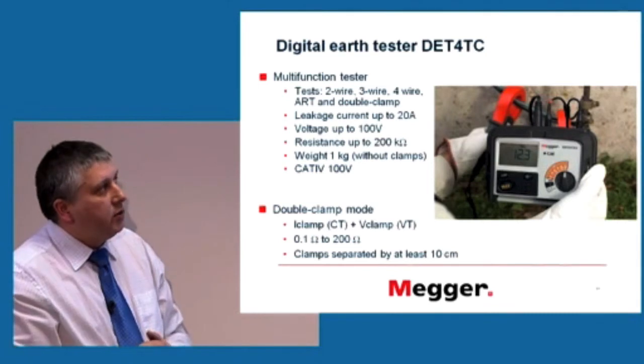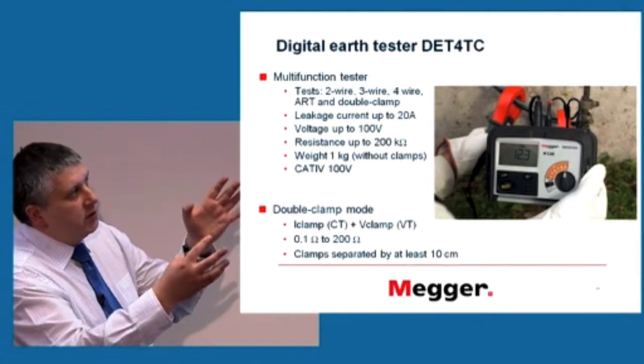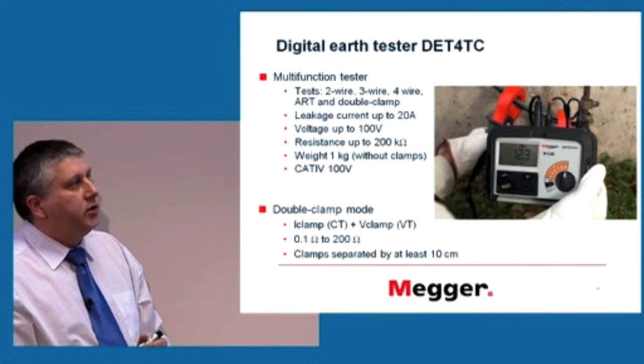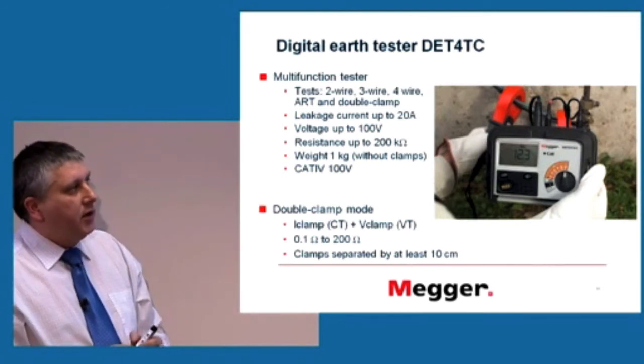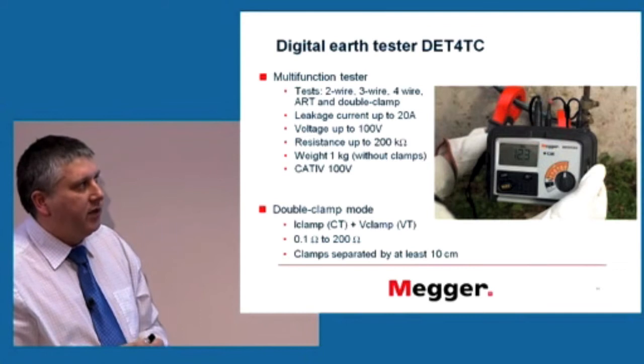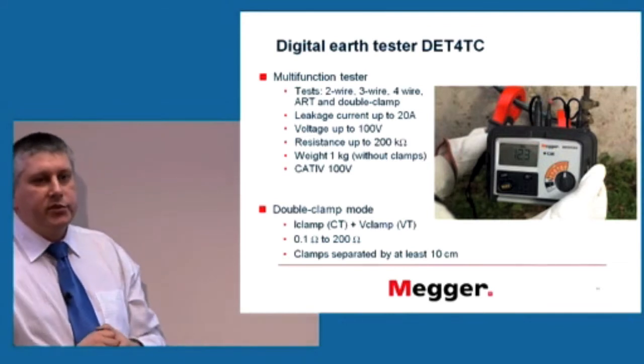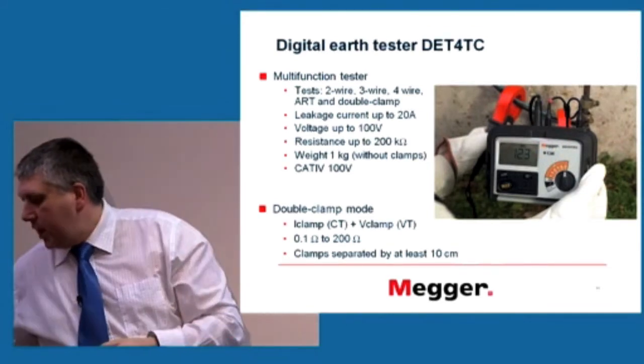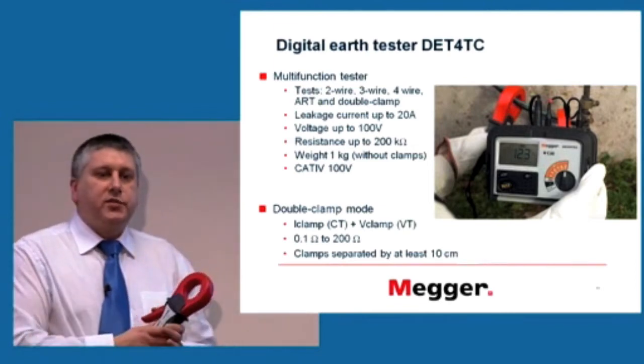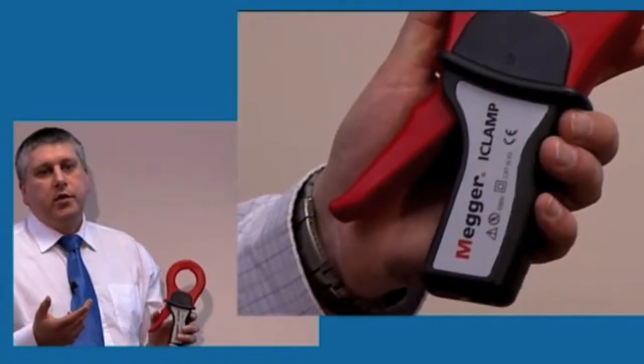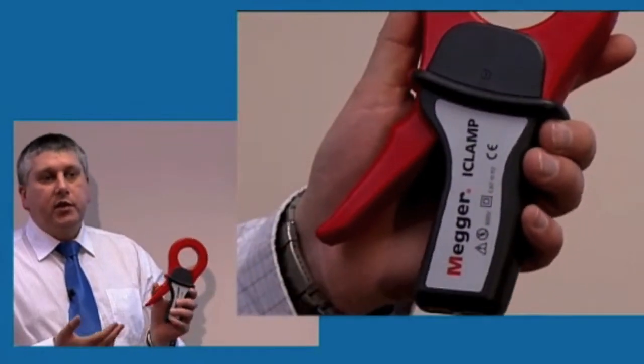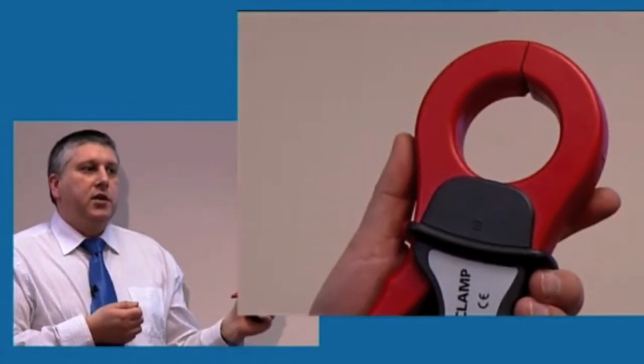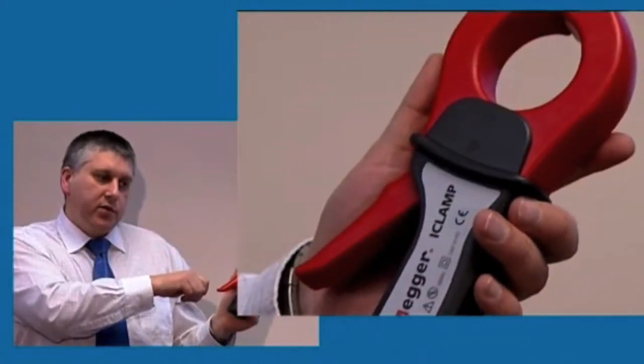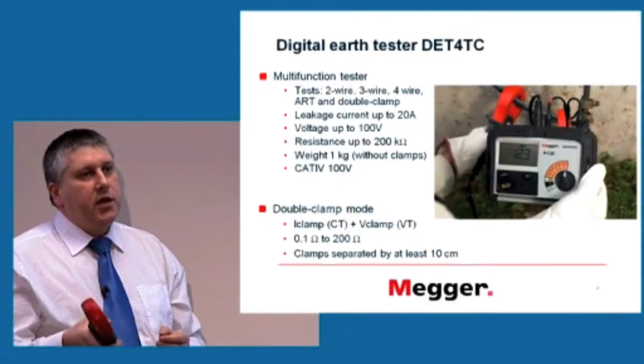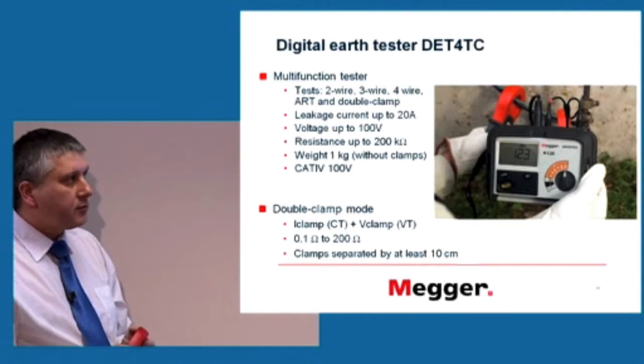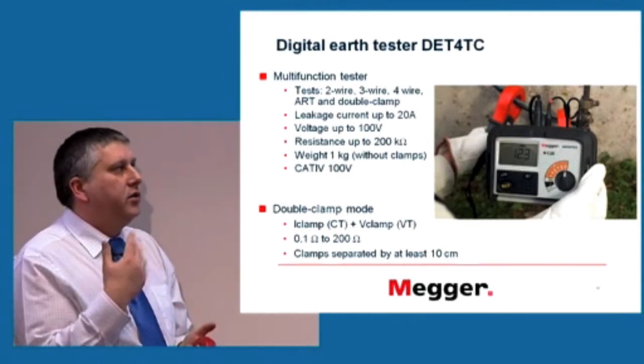So this is how it was done. There was a device with the two transformers connected to it. You can't see it in this picture, but that switch is positioned at the double clamp method. And you can clearly see the two red clamps. Basically, the same clamp is used as a voltage transformer and as a current transformer, because it's just a transformer, as I said at the beginning. It's just a number of turns. So one clamp is driven to generate some voltage in the loop. The other clamp works as any current transformer and measures the current. And then the resistance is calculated.